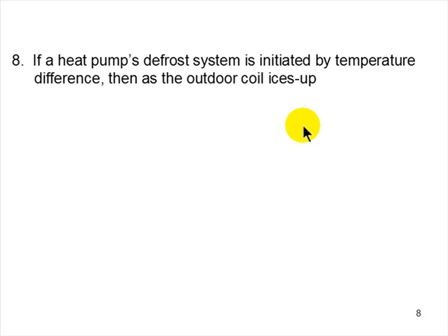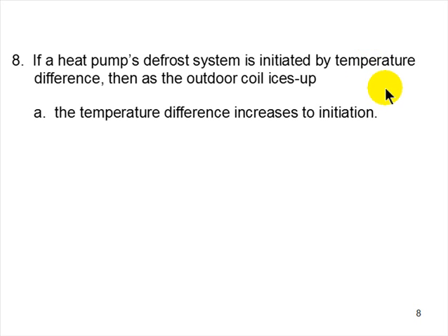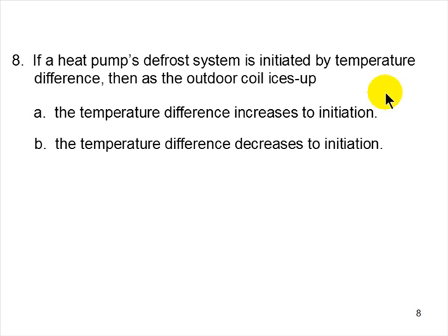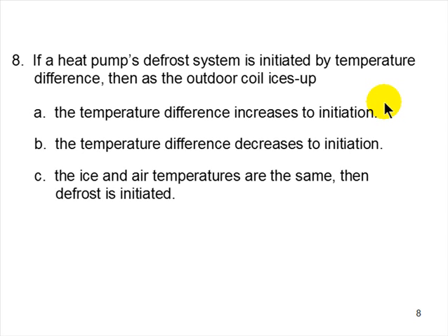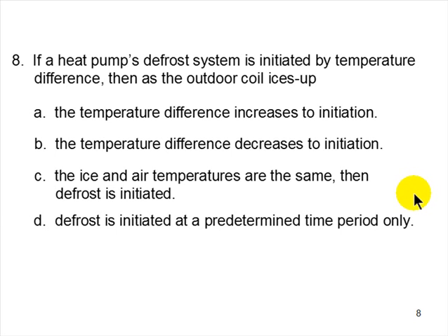Eight, if a heat pump's defrost system is initiated by temperature difference, then as the outdoor coil ices up, the temperature difference increases to initiation. The temperature difference decreases to initiation. The ice and air temperatures are the same. If the ice and air temperatures are the same, then it's going to go into defrost, or defrost is initiated at a predetermined time period only. If you got temperature sensitive, what happens? Yeah, temperature difference increases to the point where it initiates defrost.